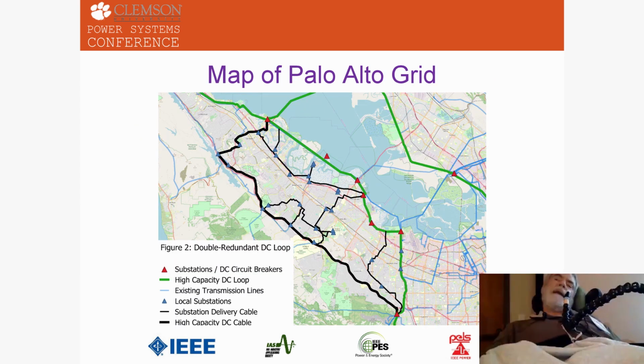The next map zeroes in on a portion of the previous map, adding cable connections as well as the DC loop connection. The large green line is the DC loop 15,000 amp connection. The heavy black line is 800 amp, and the smaller ones are 285 amp. For reference, the 800 amp connection is 300 megawatts.